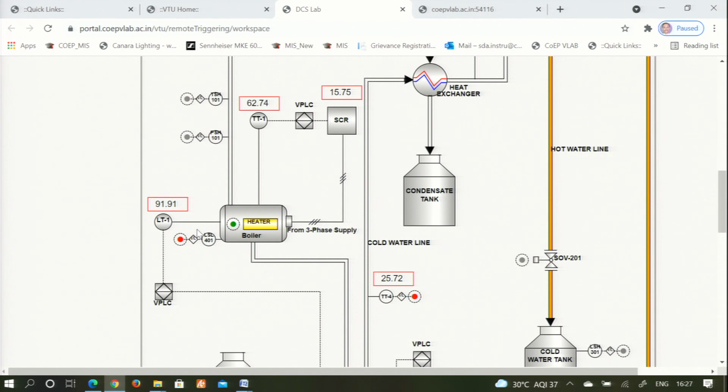If you miss that, still there is a master program in our server, which keeps on checking such things which are critical. This is called the second level of safety, where the master program will check whether the safety command is violated or not. If it is violated, it will stop the plant, indicating to you that you violated the safety.